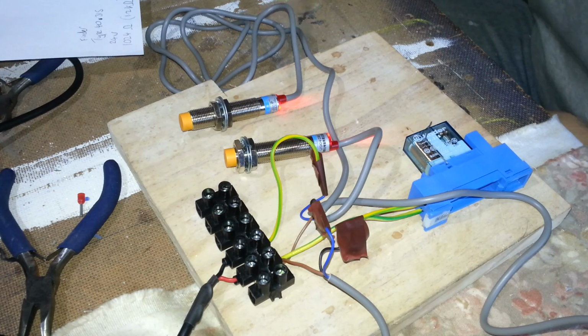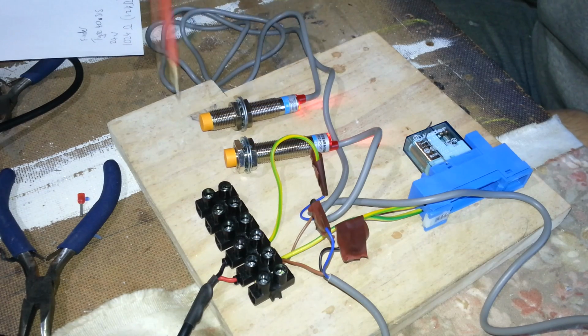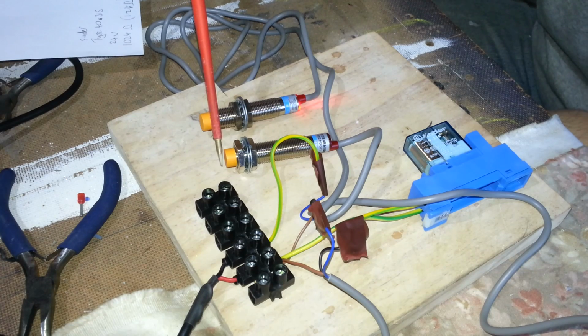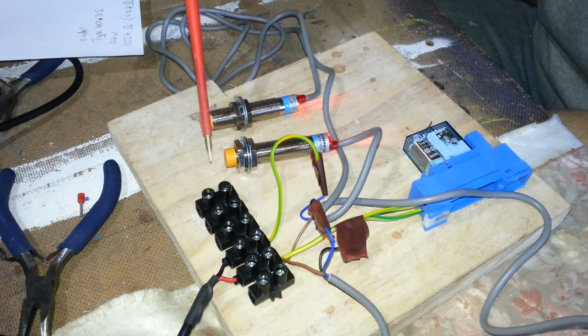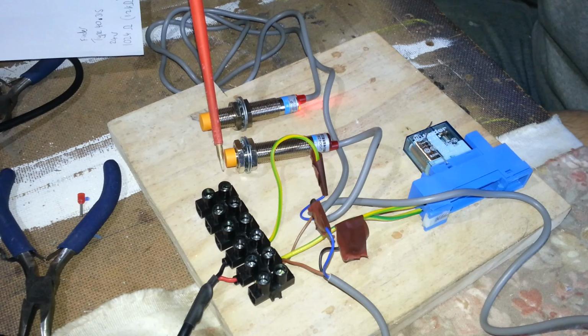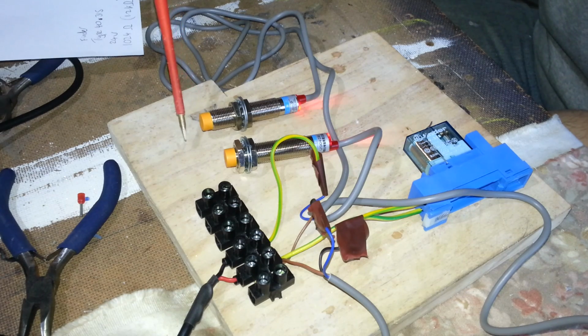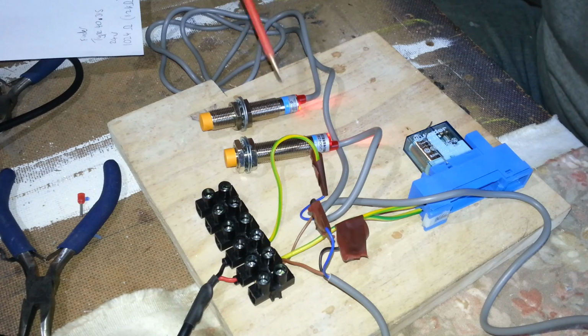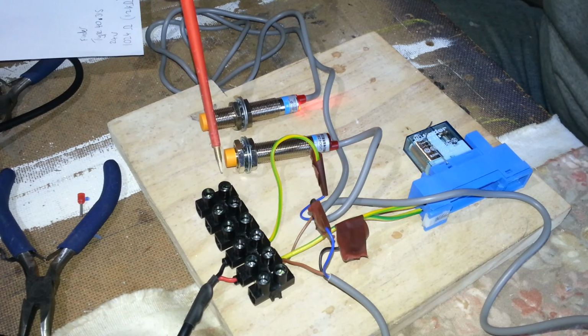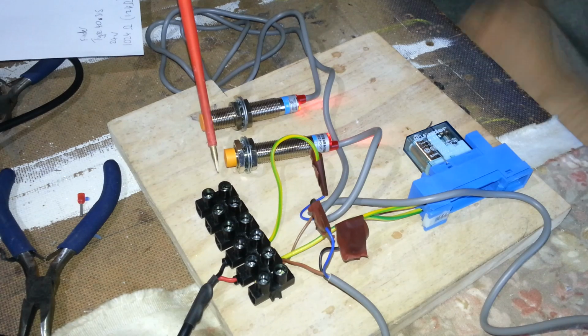Now, the unexpected behaviour. Watch the lights on the sensors. So this is sensor one, and when metal approaches it, it goes off, as you'd expect. The switch opens and the relay disengages, exactly as you'd expect. But notice the light on sensor two, it's still on, indicating the switch is still closed. If I go near sensor two, notice they both go off. Now, I wasn't expecting this, because these are switches in series. So when you open one switch, you'd expect all the lights to go off, but they don't.